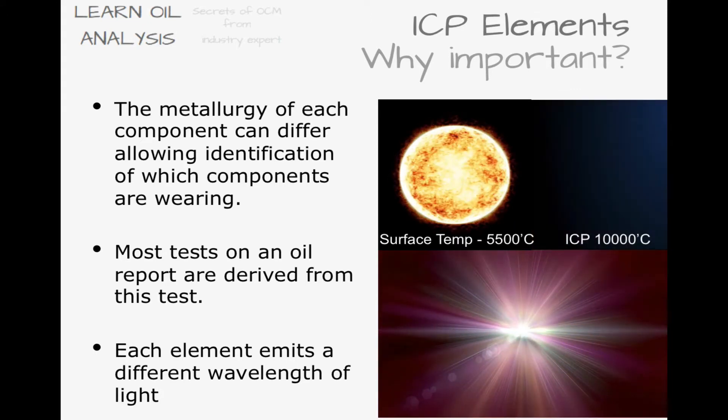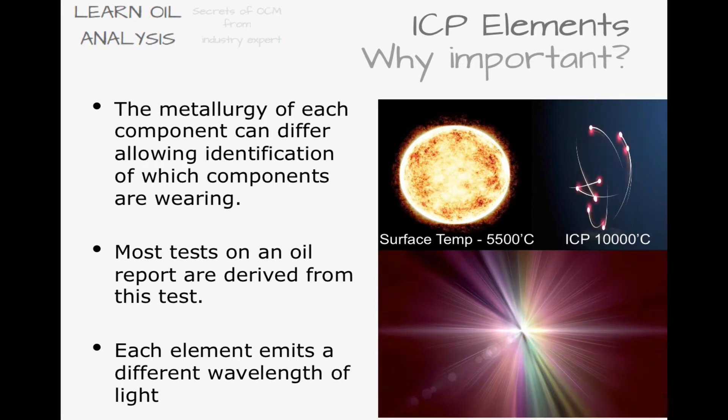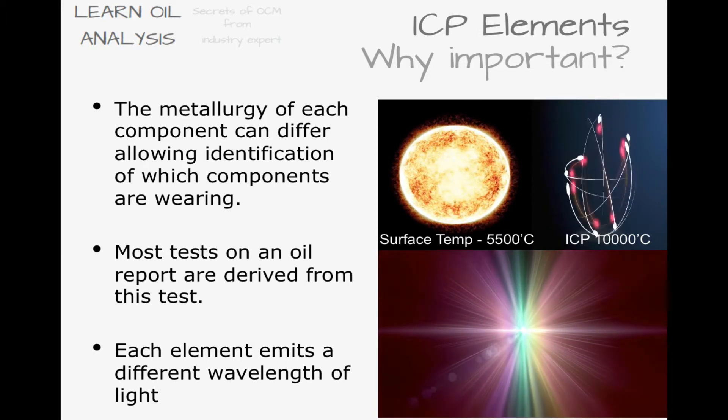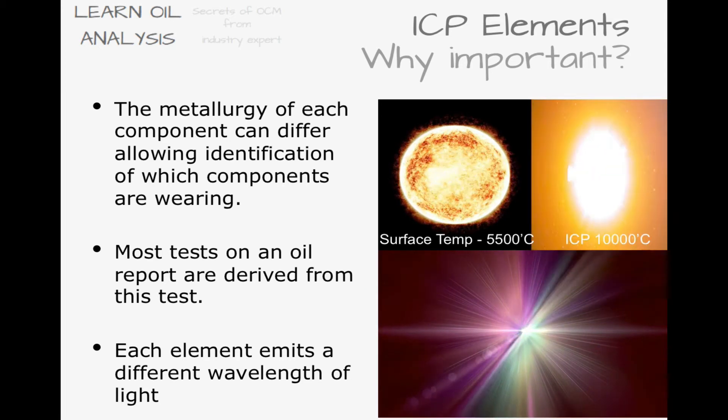Determining the mix of elements present such as aluminium, copper, or iron allows a diagnostician to determine the components wearing, so corrective maintenance can be performed before catastrophic failure.